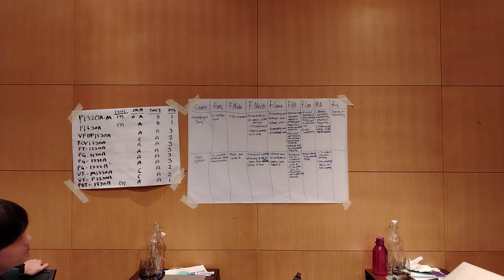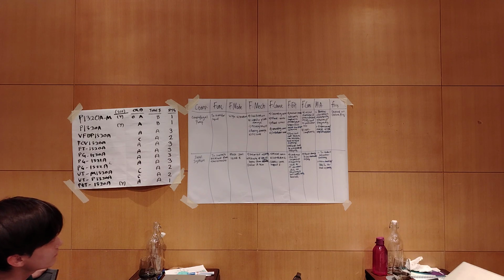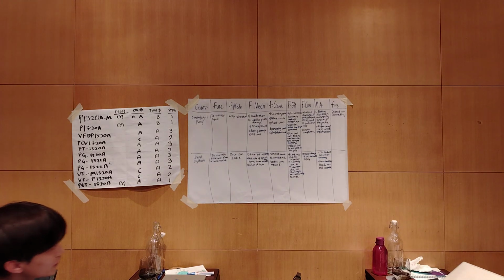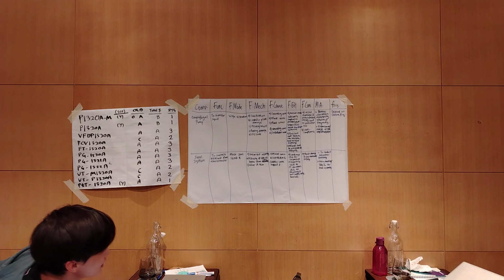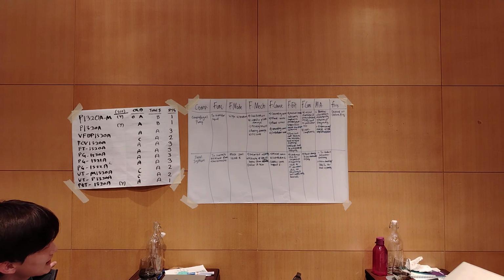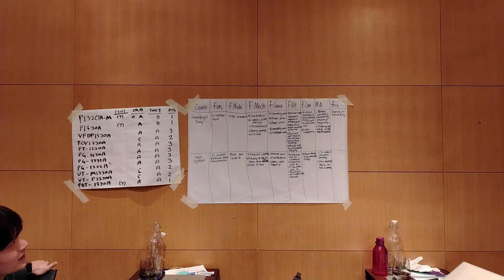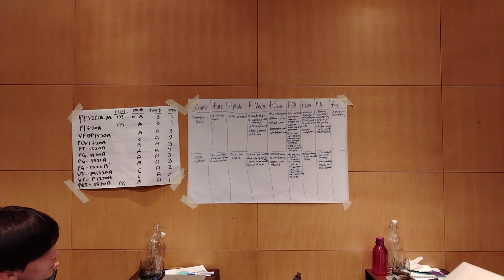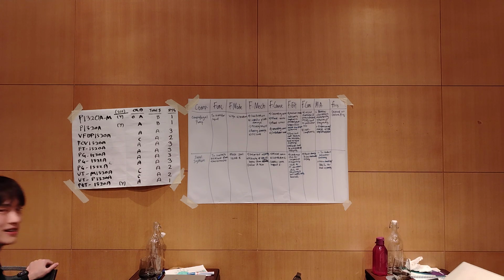Management planning error. And for the effect, first is leakage due to incorrect assembly leading to high vibration, due to bearing not sufficiently lubricated. The consequence is asset damage and environmental safety. For the mitigating actions, I think this one should be corrected. What we wrote is to conduct a refresher training for our staff and also a new checklist for the seal assembly. So probably that should be revised further.